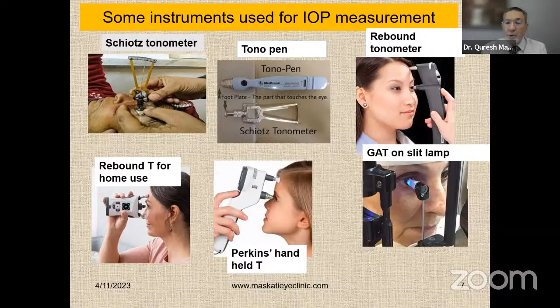The gold standard is what is called Goldmann applanation tonometry, or GAT, which is done only by the eye surgeon on a slit lamp microscope. The machine is attached to a slit lamp. We put a drop of dye in the eye called fluorescein, and there is a conical device that touches the cornea and presses on the cornea. So the pressure on the cornea is resisted by the pressure inside the eye. The more pressure I need with that plastic cone to make the cornea flat, the higher the patient's pressure. That is the principle.